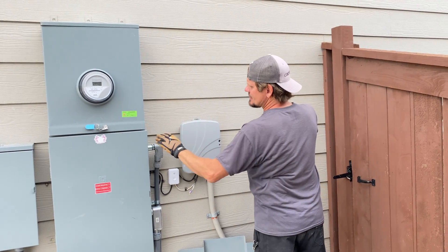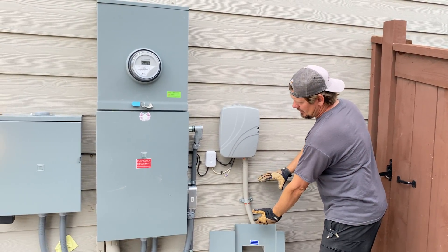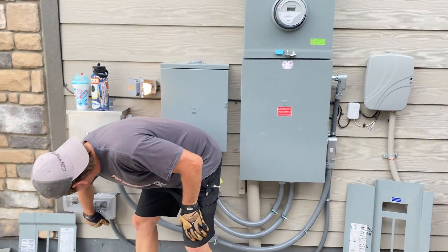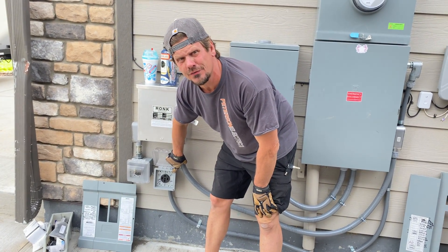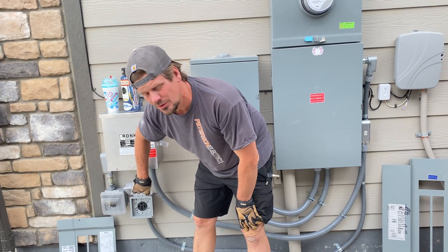I wish these guys would have had their boxes a lot lower, but I worked around it. This three-quarter-inch conduit is for an RV plug — they asked me for that. In case friends come over, you're going to want a four-wire 50-amp. This is no different than a Tesla plug; they could do a Tesla plug here.